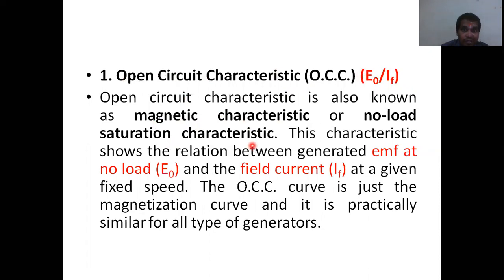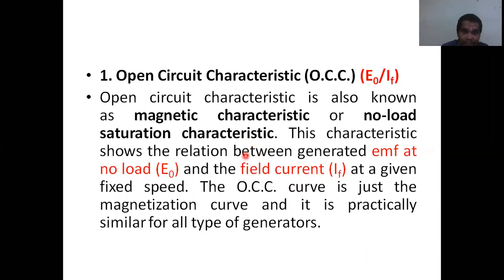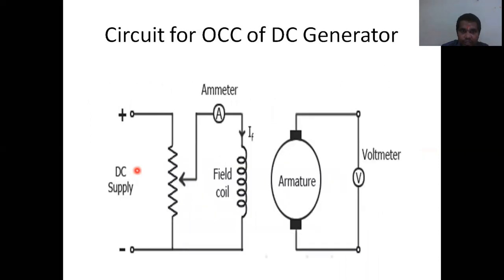We obtain the open circuit characteristics by increasing the field current gradually, and the corresponding terminal voltage is recorded from the voltmeter under no-load conditions, keeping the speed constant. For a particular speed, the field current is varied and the corresponding no-load voltage is measured across the armature terminals when no load is connected.